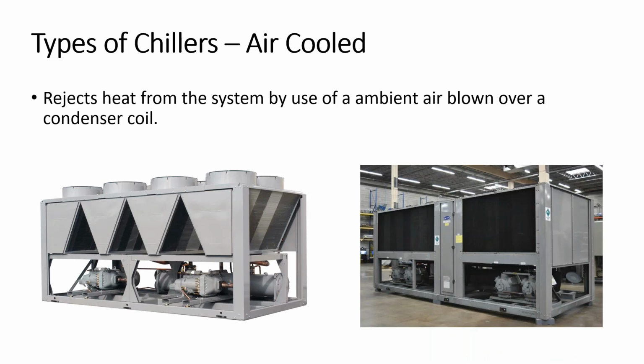So the types of chillers, and these are industry standard packaged air-cooled equipment, and they're very convenient. You can buy this package and you just pipe up the chilled water side to it. This is air-cooled. It rejects the heat to the ambient air through a condenser coil. You see these coils in that section along with the fans on top, or they're on the horizontal so you can see them. The diagram on the left are rotary compressors. The picture on the right are reciprocating compressors, and we'll talk a little bit about those in a minute.